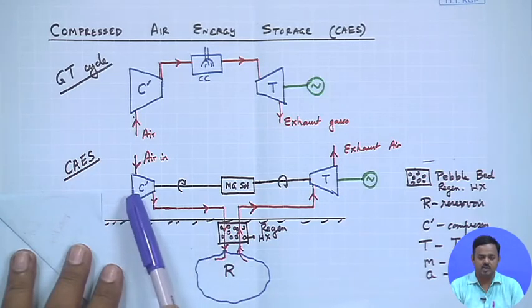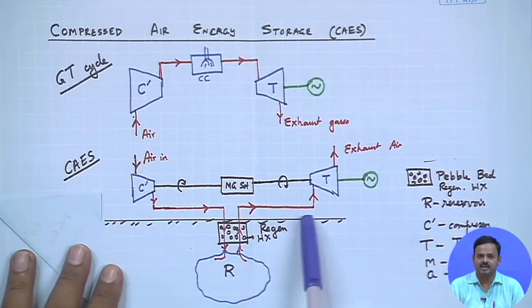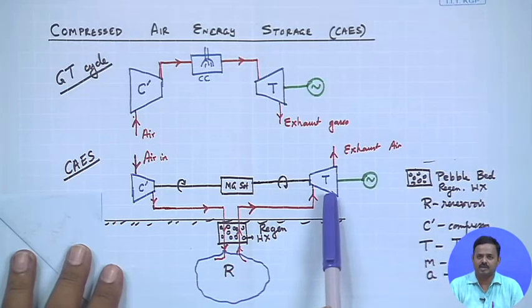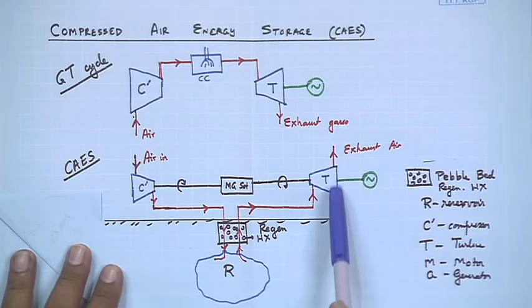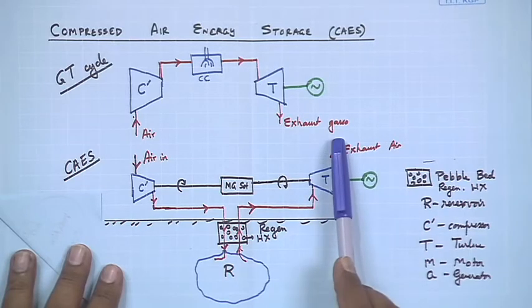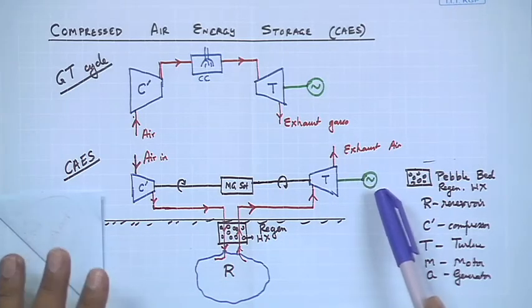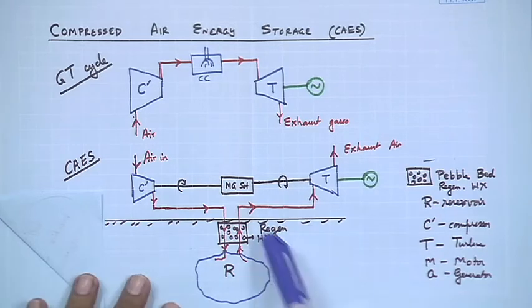This compression occurs during off-peak hours when we have excess energy, so we use that extra energy to run the compressor. During peak hours, when we need the energy back, the compressed air is fed to a gas turbine — an air turbine — where it is expanded, its pressure comes down, and the exhaust air exits the turbine.